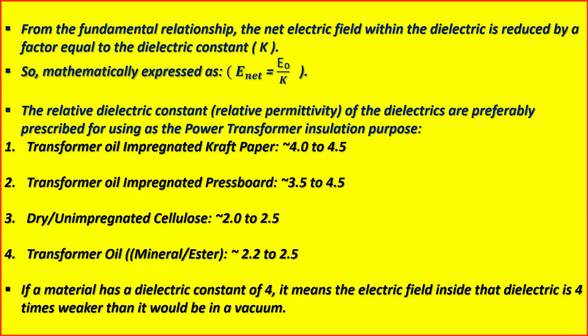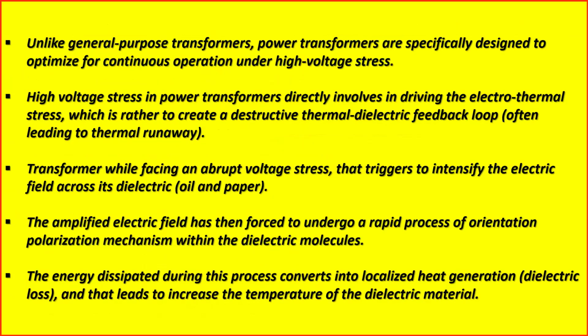Last, transformer oil, mineral or ester, is 2.2 to 2.5. If a material has a dielectric constant of 4, it means the electric field inside that dielectric is 4 times weaker than it would be in a vacuum. Unlike general purpose transformers, power transformers are specifically designed to optimize for continuous operation under high voltage stress. High voltage stress in power transformers directly involves driving the electrothermal stress, which creates a destructive thermal dielectric feedback loop, often leading to thermal runaway.